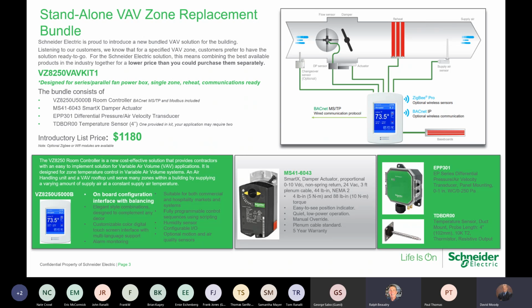So George, in a case like that, you could use a transducer if you needed to, a 0 to 10 volt staged transducer, right? So if you didn't have enough outputs. That's fine. I mean, we don't see 4 that often, but there's a capability. Definitely 2, and not including baseboard. So definitely a 2-stage reheat box is pretty common. Yeah, and that would be easy to do in Lua. Okay. Yeah, easy enough to do in Lua for it.